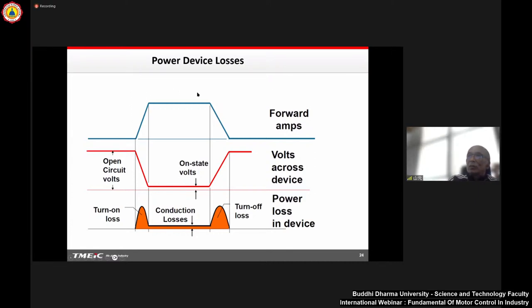Back in the 1990s, during the GTO period, drive efficiency was most likely around 90-91%, very low efficiency, because the switching speed was very slow, making switching loss very high. That's why GTO drives could not achieve good efficiency -- 91-92% was the maximum at that time.